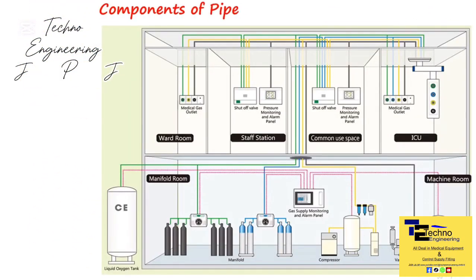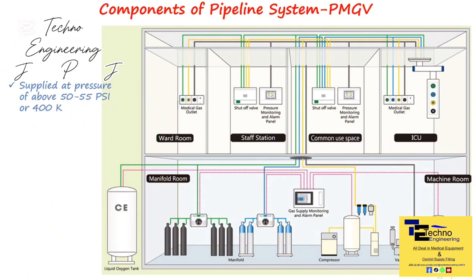Piped medical gas and vacuum, abbreviated as PMGV, is a system in which gases are delivered from central supply points to various locations within a hospital at pressures exceeding 400 kilopascals, 50 to 55 psi, or approximately 4 bar, 3000 millimeters of mercury. The conversion of these units was discussed in the basic physics section of this playlist, specifically in the cylinder section.